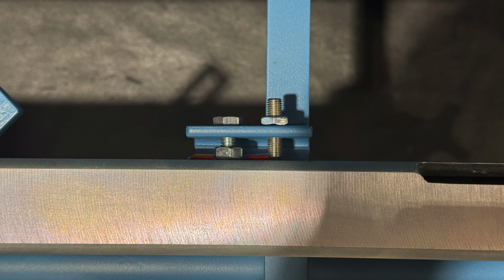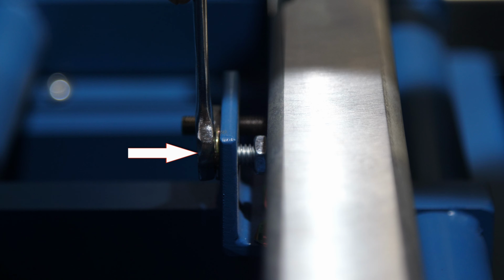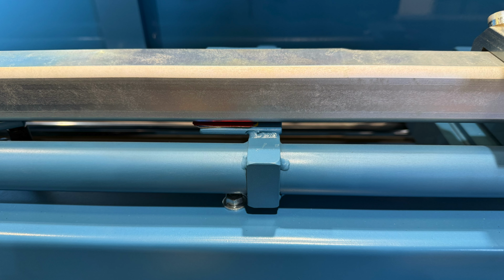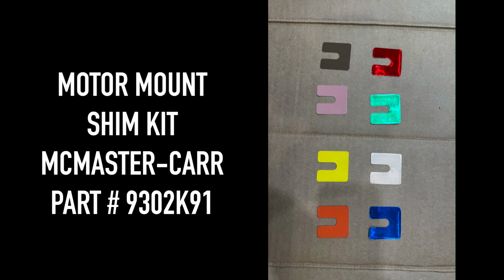You should be able to move the V-support bar up and down at this point. If your front face is also out of spec, like your top face, then you can loosen up this jam nut with a 7/16 wrench because you'll need to use the adjusting bolt in a few minutes. Now, if your top face is out of spec, you can use shims between the V-support bar and mounting bracket to get you within 2/1000ths of an inch on the top face. You'll add or remove shims as needed. Again, you can get these motor mount shims online.